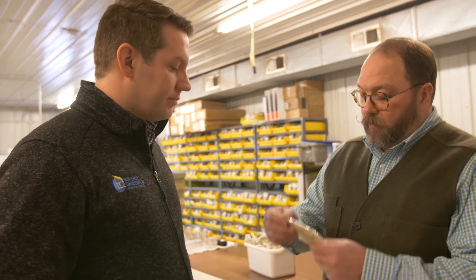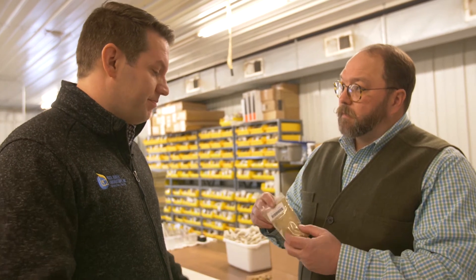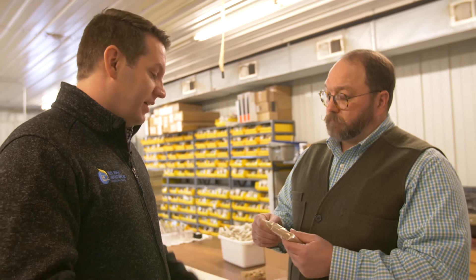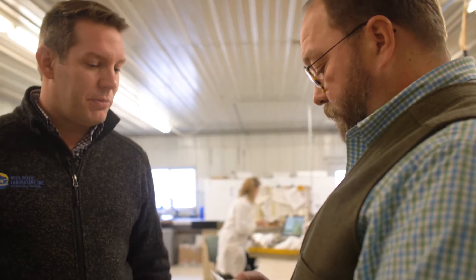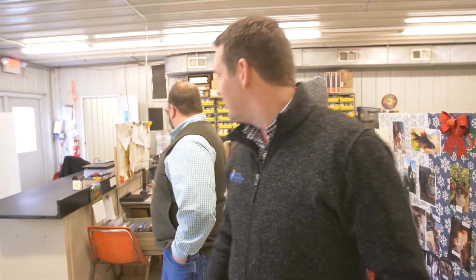So after we grind it, we're looking at something like this — a powder sample. From this point it's either going to be filled into an NIR disc or sent back through the wet chemical lab. It only takes a small portion — you just scoop with a kitchen spoon into a disc, only a couple of grams. We keep those cataloged for several months; we actually keep the live original sample for about a week. What Ryan's doing here is loading up discs with the dried and ground sample and then feeding them on the ramp to the NIR.